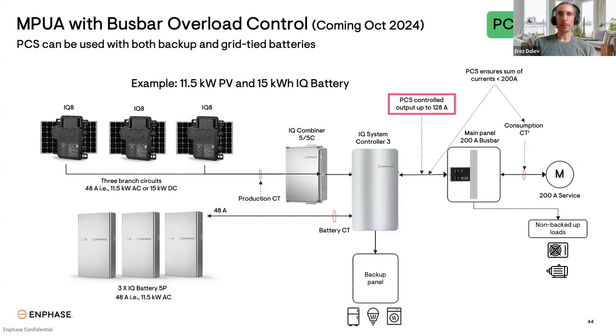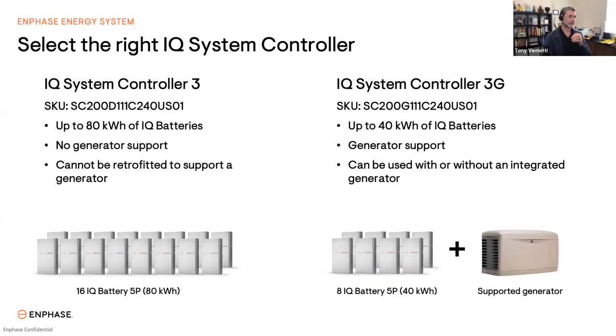And another question here from Team Soto. When stacking batteries, do you run them in parallel or daisy chain? Oh man, I don't have that level of knowledge of system design, but they appear to be daisy chain. But I think when you're talking in terms of electrically, how they're supplying power into the controller, they are in parallel. So, if you've got five 5P batteries on a system, they can be connected side by side, and one set of wires goes through and connects all those 5P. You don't have to have like 5 sets of conduit coming out and going into the system controller. You just have all those batteries interconnected with very short conduit pieces, and the wiring just runs through those conduits across the 5 batteries in that example.